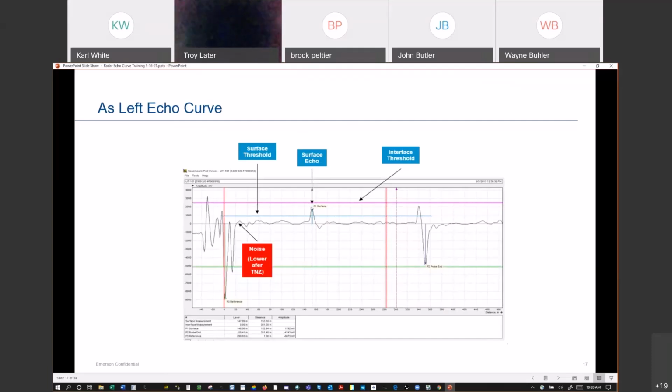Generally, you picked a probe that isn't actually on the device, and it's offsetting it by 8 inches. So that's kind of a ticker for me. It could be an inch off, but if it's much more than that off of zero, it's got a problem. So I definitely look for that, and I make sure it's crossing the green line.